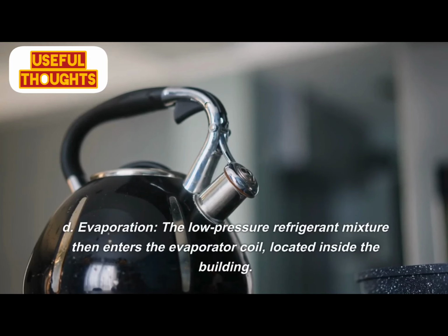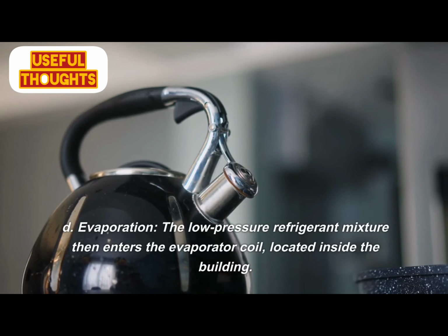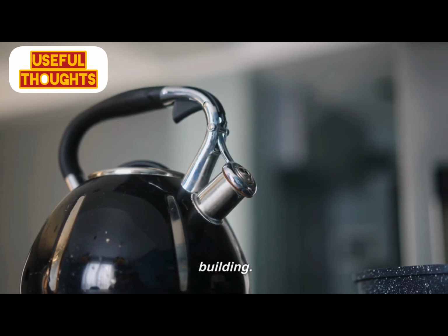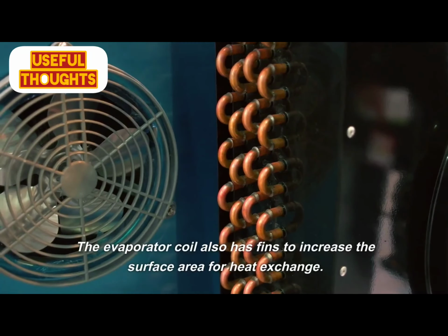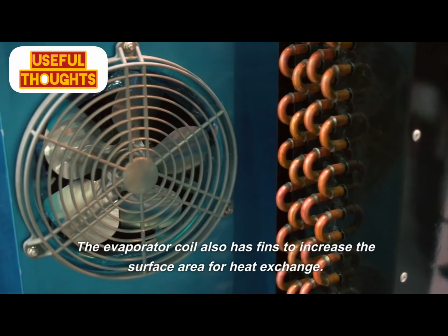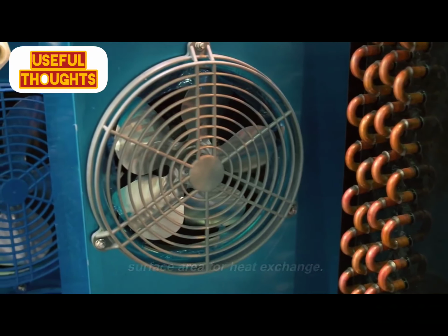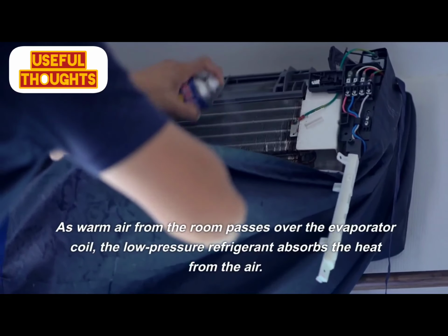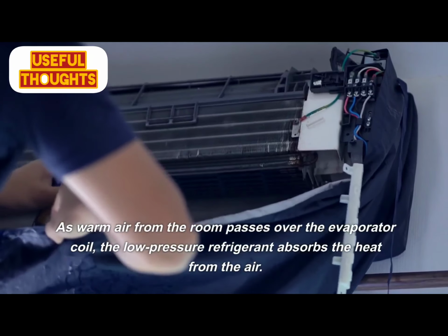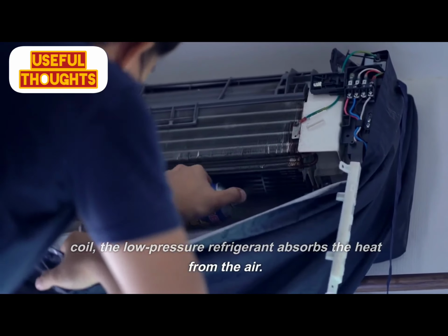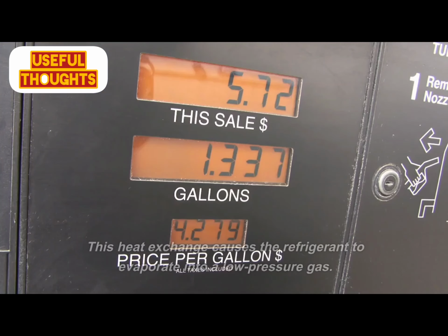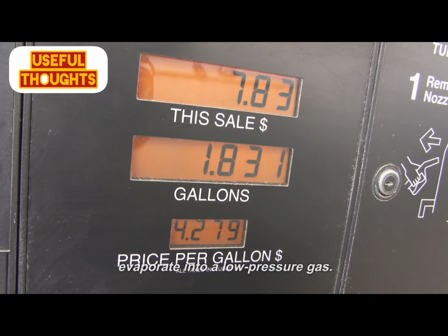D. Evaporation. The low-pressure refrigerant mixture then enters the evaporator coil, located inside the building. The evaporator coil also has fins to increase the surface area for heat exchange. As warm air from the room passes over the evaporator coil, the low-pressure refrigerant absorbs the heat from the air. This heat exchange causes the refrigerant to evaporate into a low-pressure gas.